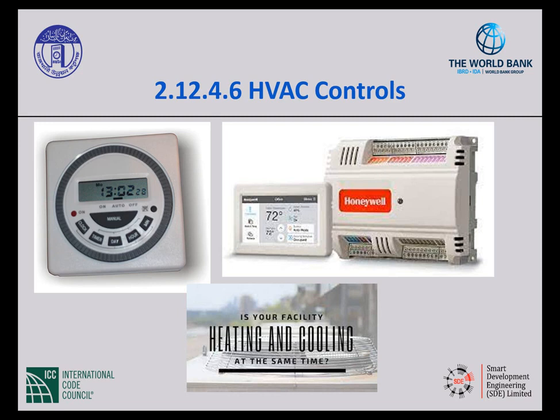What this is trying to tell us is, don't run the air conditioner to the point where it turns the furnace on, and don't run the furnace to the point where it turns the air conditioner on, so you're sitting there heating, cooling, heating, cooling. You need a 5-degree deadband in there. It heats to a certain point, but it has 5 more degrees before that air conditioner will turn on. The likelihood is that it won't reach that, and it'll go back into heating mode. Or vice versa, you cool to a point, but you have 5 degrees before it actually is going to turn that furnace on, and likely it won't. And so that's what this section is asking us to do, to keep from simultaneously heating and cooling the building.